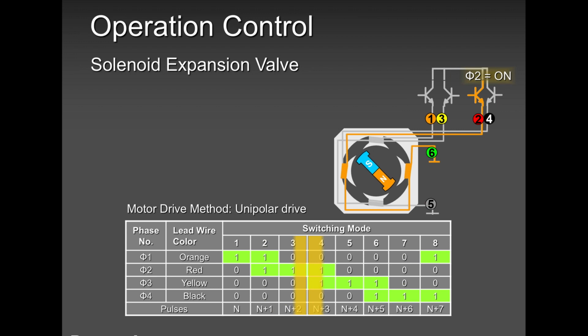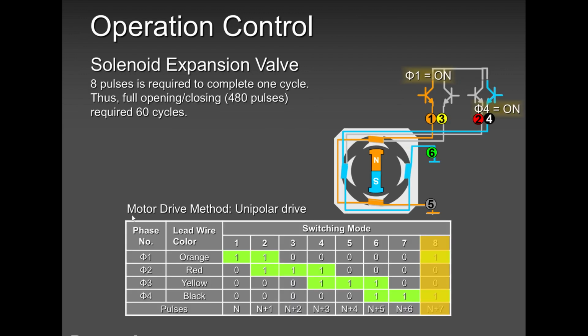So what is this electronic valve about? It's all about magnetism. It has a magnet inside. It works on power, and depending on the pulses, it will ramp up and down. 8 pulses are required to complete 1 cycle. The full operating cycle is 480 pulses. We cannot see that on our laptop or anything like that. It's embedded in the EEPROM. But the same electronic expansion valve on the commercial side, where you can hook up your laptop, you can see how it modulates, how it goes higher, how it goes lower, depending on the heat load.